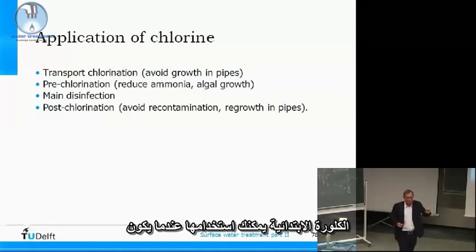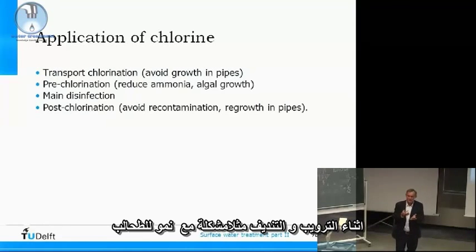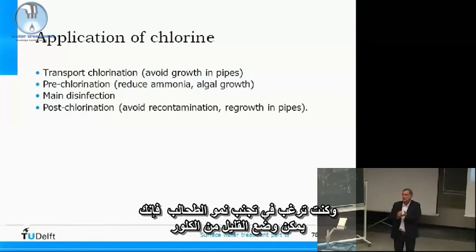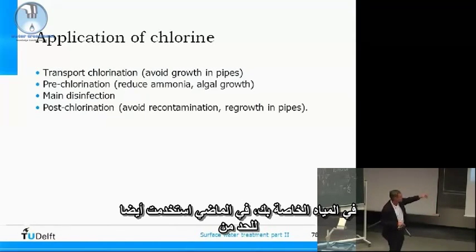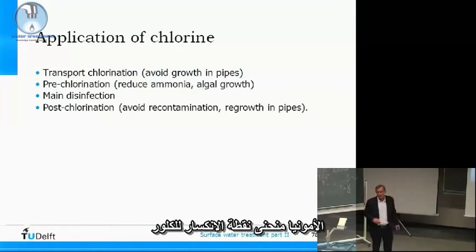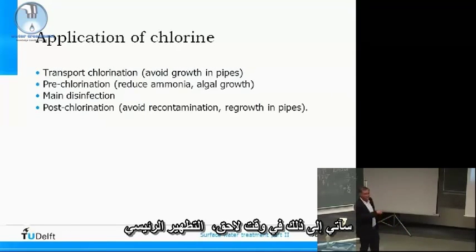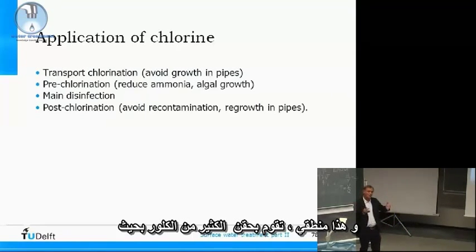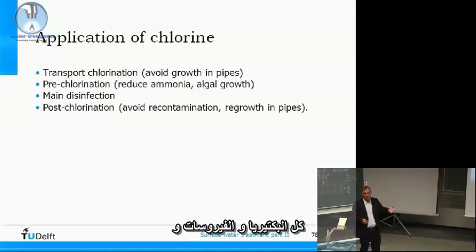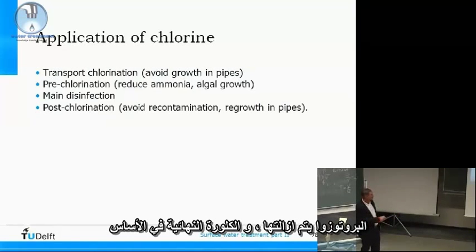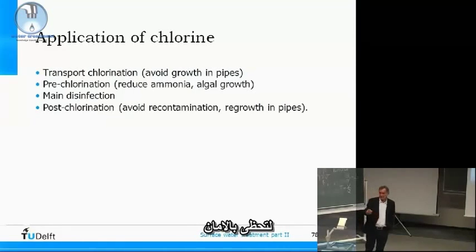Pre-chlorination can be used when, for example, during your coagulation and flocculation system you have problems with algae growth and want to avoid it — you can put a little bit of chlorine in the water. In the past, it was also used to reduce ammonia via breakpoint chlorination. The main disinfection is straightforward: you dose enough chlorine so that all bacteria, viruses, and protozoa are removed. Post-chlorination is mainly to maintain a safety chlorination during distribution.